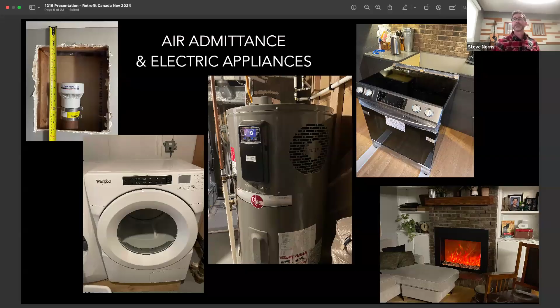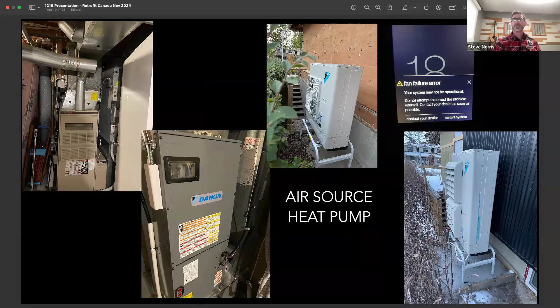We swapped out our natural gas furnace for a fan coil, which looks similar but just has a backup electric element instead of gas burners. One of the learnings was that we didn't do a proper F280 heat load calculation when we did the retrofit, so we ended up under capacity with the first heat pump that we had installed and had to upsize it after the fact.